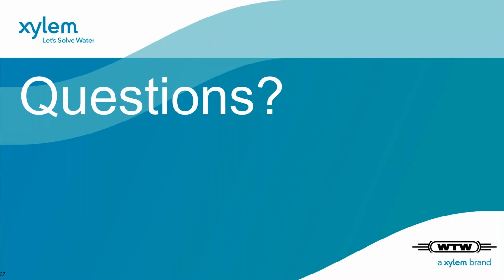Okay, thank you. Which model should be selected for use with seawater? As I mentioned before, it is not suitable for seawater applications, as an adjustment of reagents would be needed, and the material as well. The maximum chloride concentration is 500 milligrams per liter or below.